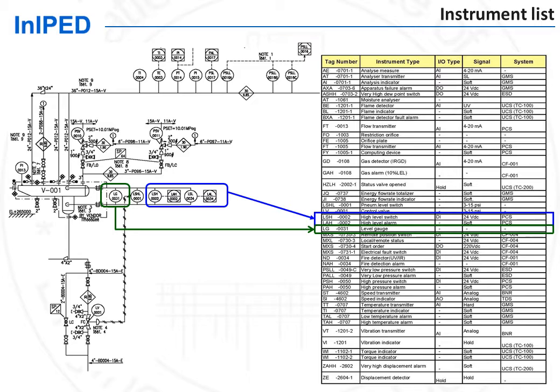Once the instrument list has been produced, each field instrument must be specified. A data sheet is produced to this end. A process data sheet has already been issued for some instruments, such as control valves, pressure safety relief valves, and flow instruments. For the other instruments, the process information is available on the heat and mass balance.